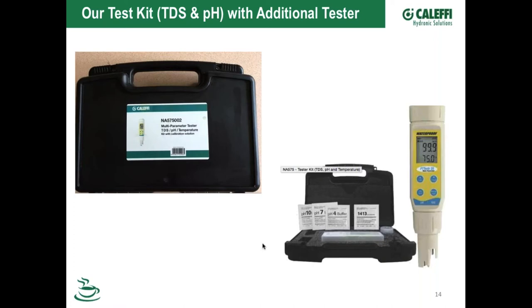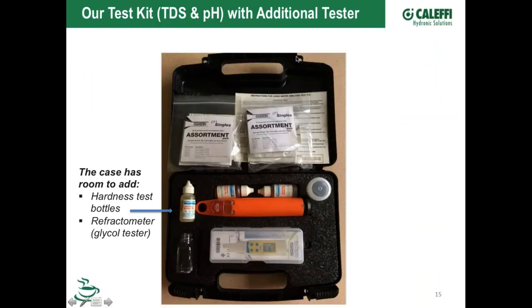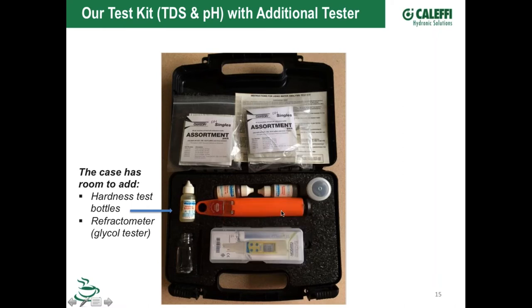So I said, you know what, since there's room in that box, I found you could just take your pocket knife or an X-Acto knife and cut out the foam that's in there. So what I've done is put my water hardness test kit, which is three solutions that you drop in there, and I also put my meter that reads my glycol percentage, my refractometer. So everything I need to test for pH, test for the hardness of the water with the dropper kit, as well as the TDS meter, are all in one carrying case. When I walk in, I've got everything in there. Again, that's exactly what Jim has on his desk back there in Wisconsin when he does water testing for his customers when they come in.